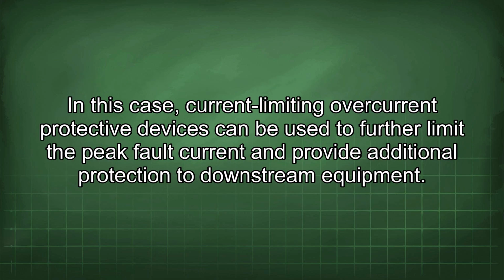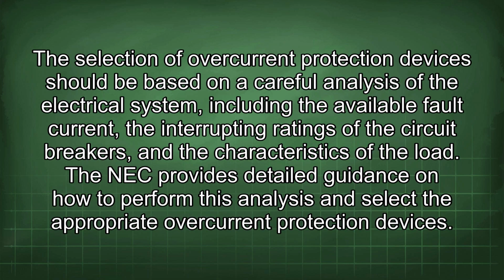In this case, current limiting overcurrent protective devices can be used to further limit the peak fault current and provide additional protection to downstream equipment. The selection of overcurrent protection devices should be based on a careful analysis of the electrical system, including the available fault current, the interrupting ratings of the circuit breakers, and the characteristics of the load. The NEC provides detailed guidance on how to perform this analysis and select the appropriate overcurrent protection devices.